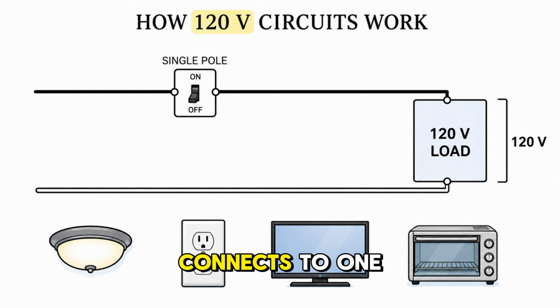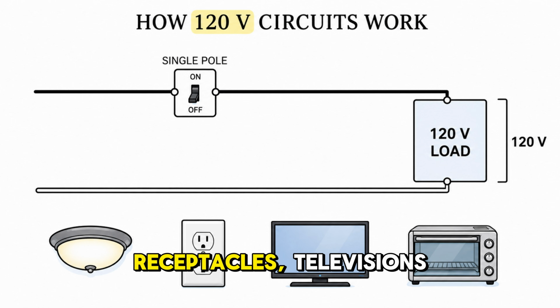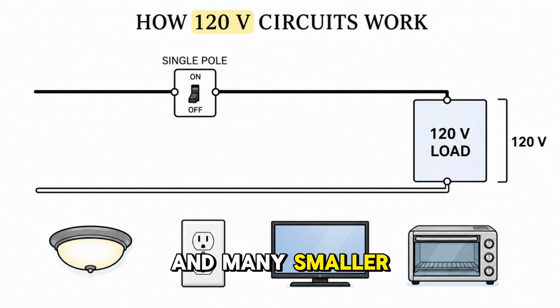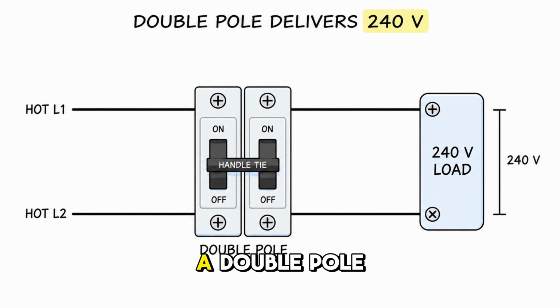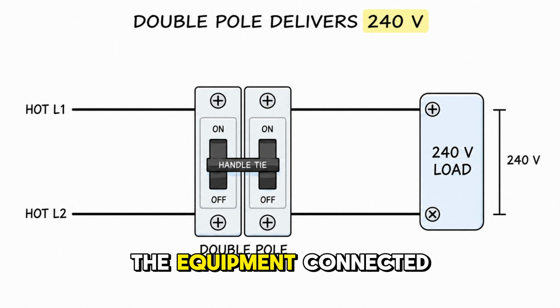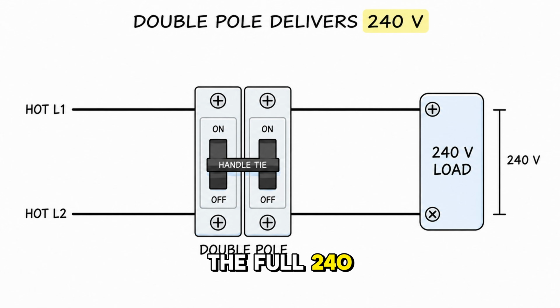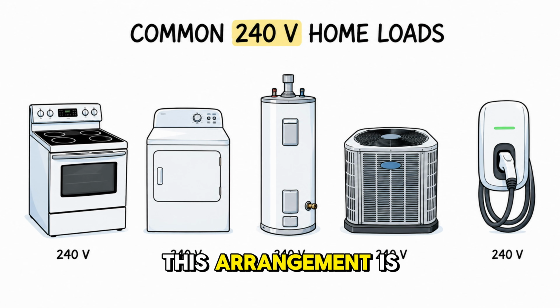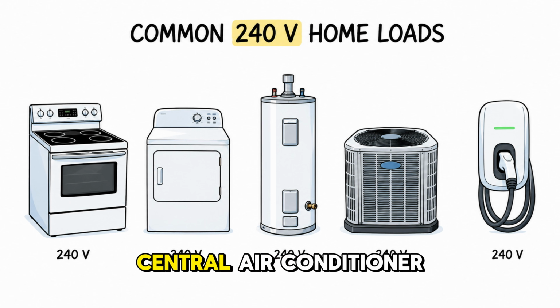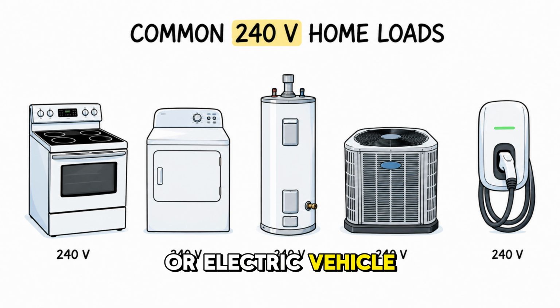A single pole breaker connects to one hot bus bar. A normal 120-volt circuit then uses that hot conductor and the neutral. This is how lights, receptacles, televisions, and many smaller appliances receive power. A double pole breaker connects to both hot bus bars at once. The equipment connected to it receives the full 240 volts between them. This arrangement is commonly used for an electric range, clothes dryer, water heater, central air conditioner, or electric vehicle charger.